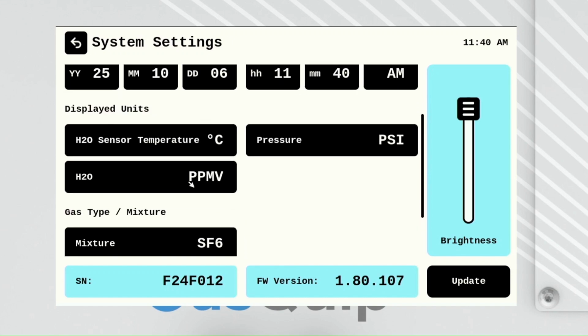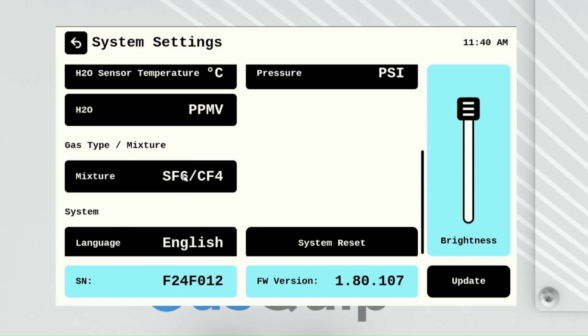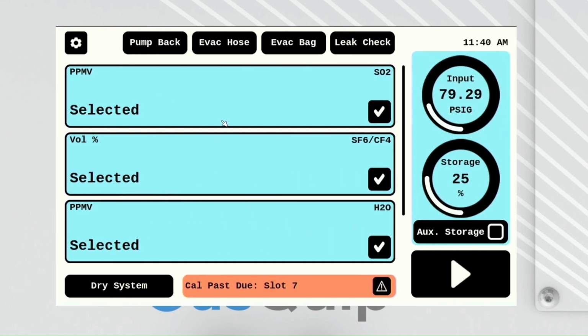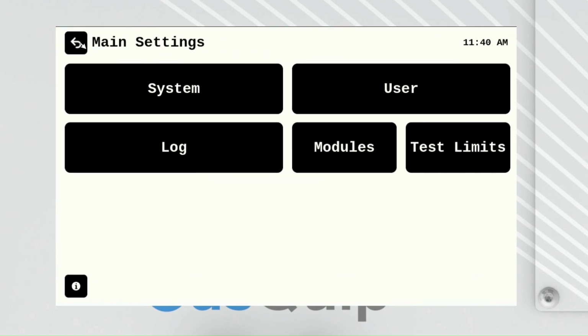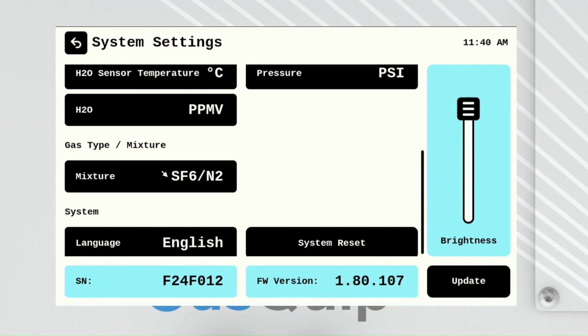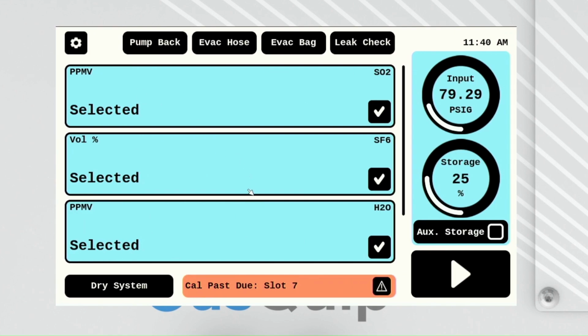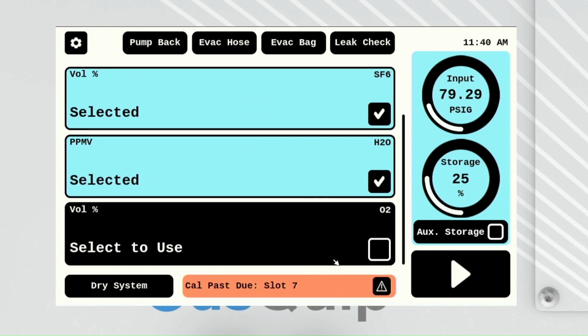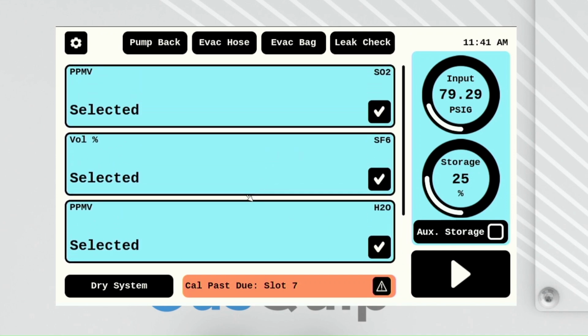The gas type / mixture tells the system what type of mixture that you are testing. So if you're testing a 60-40 gas mixture of SF6 CF4, you go back to your home screen and that will affect the readout here to tell the system that you're testing that mixture. And depending on what you are actually testing, so let's go back to SF6, it will select or deselect certain modules by default. So for example, now our oxygen sensor is deselected because we won't be using that sensor for testing either pure SF6 or SF6 on a gas insulated system.